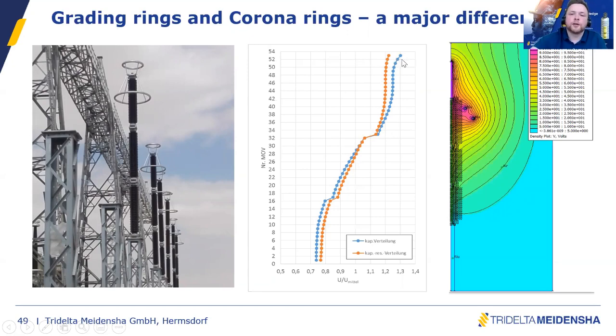So the voltage stress on the topmost varistor block is the highest, and on the lowest varistor block, the stress is the lowest. That's why we have this diagram where we see that the distribution goes from very high on the top MOV block to low on the lowest MOV block, and we can influence this voltage distribution by applying a grading ring on top. You see on the diagram here on the right side, we made a FEM analysis where we see the voltage stress and how we can shield it, how we can improve the distribution along the complete surge arrestor length.